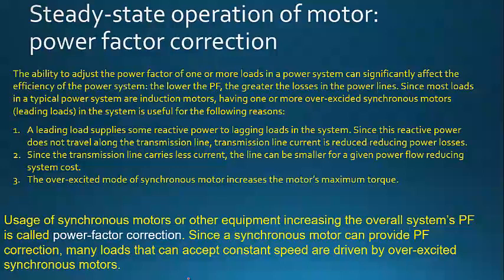So we were having a lagging power factor, and with that one, we had higher losses in the power system. Since most loads in the power system are induction motors, we can't adjust the excitation or the power factor of an induction motor.